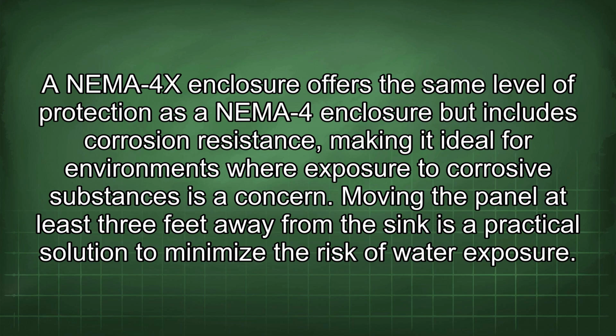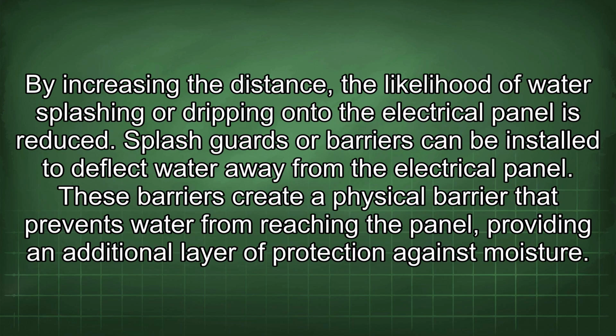Moving the panel at least 3 feet away from the sink is a practical solution to minimize the risk of water exposure. By increasing the distance, the likelihood of water splashing or dripping onto the electrical panel is reduced. Splash guards or barriers can be installed to deflect water away from the electrical panel. These barriers create a physical barrier that prevents water from reaching the panel, providing an additional layer of protection against moisture.